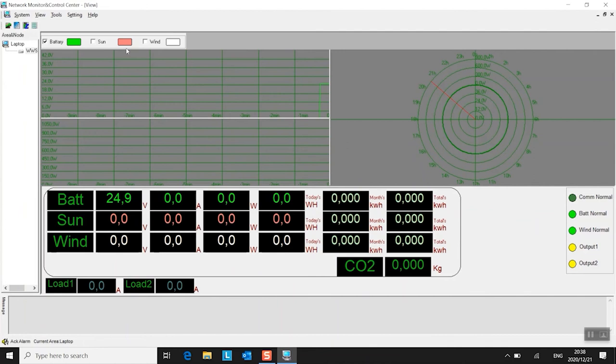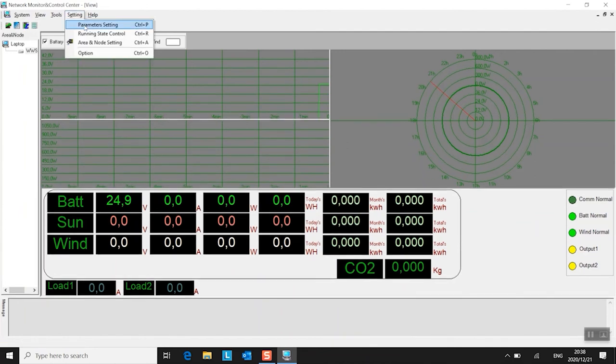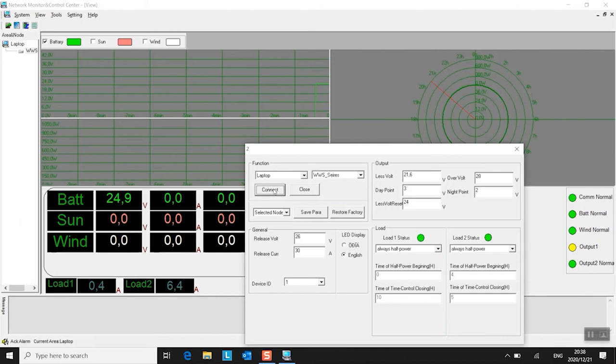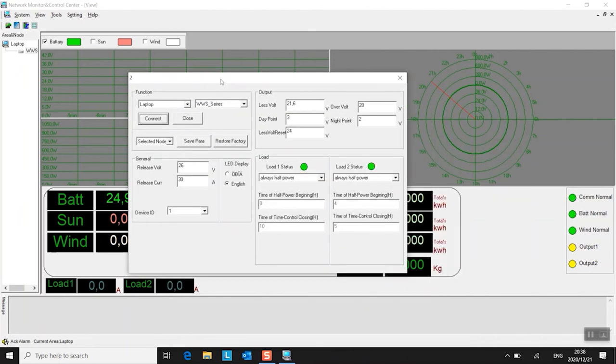Now you've got to run that again. Parameter settings. Click connect. There's the laptop and the WWS series. And now you're able to change settings on that unit. Now just now it was set at 27 volts. I changed it to 26 just to make sure it's all working properly. So I'm going to change it back to 27.